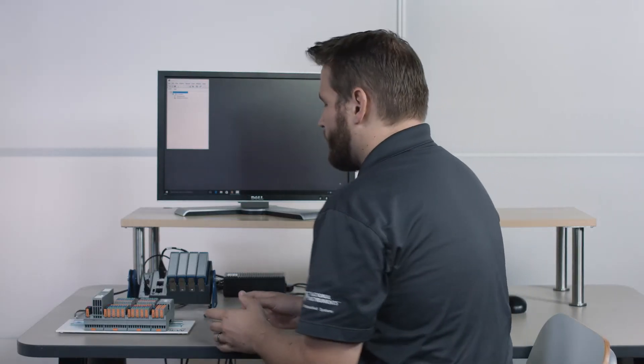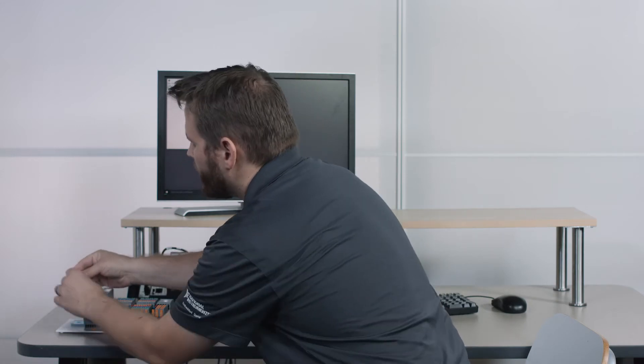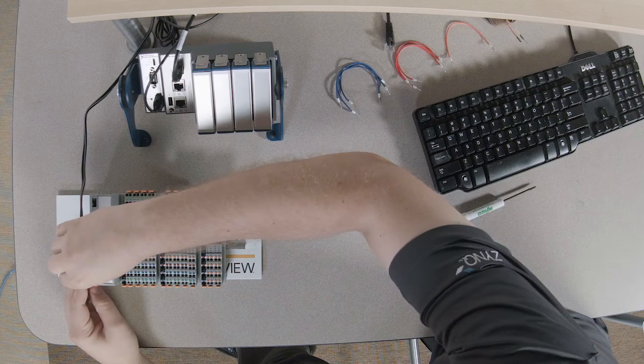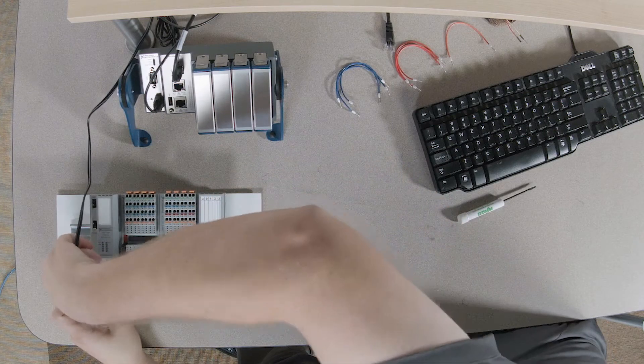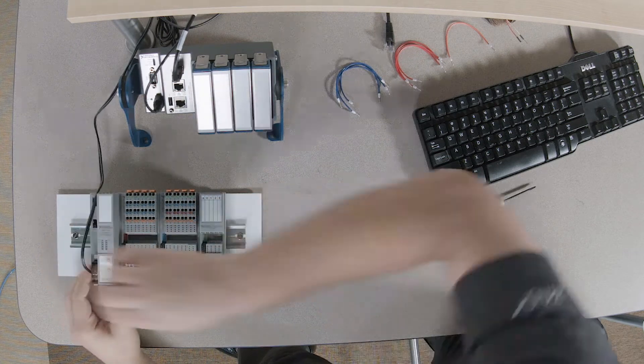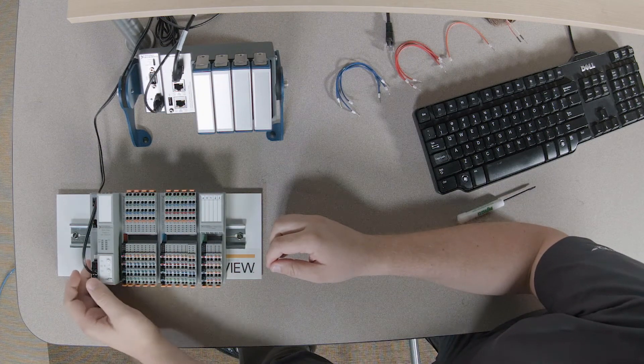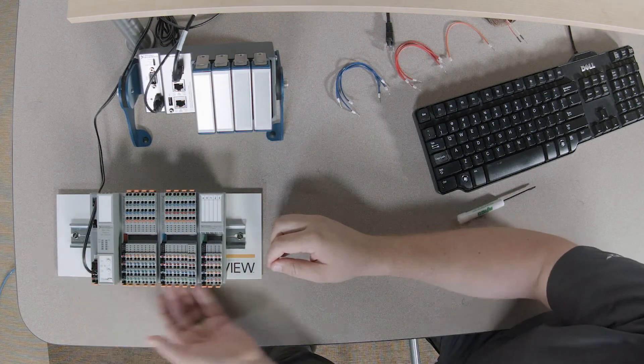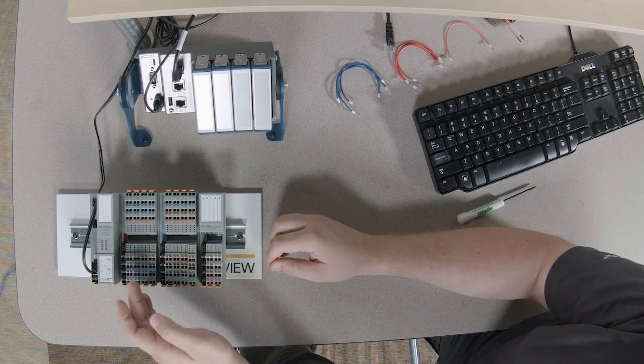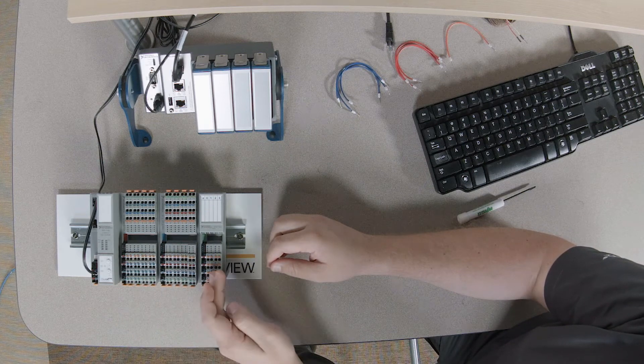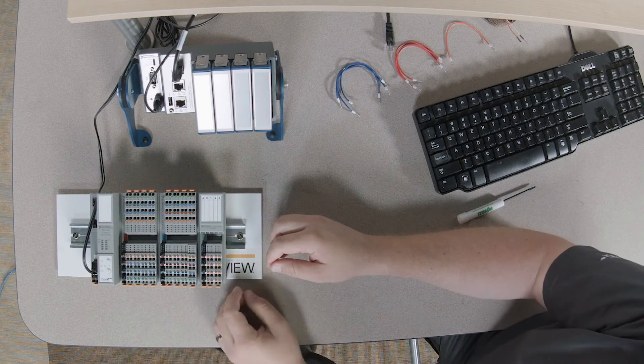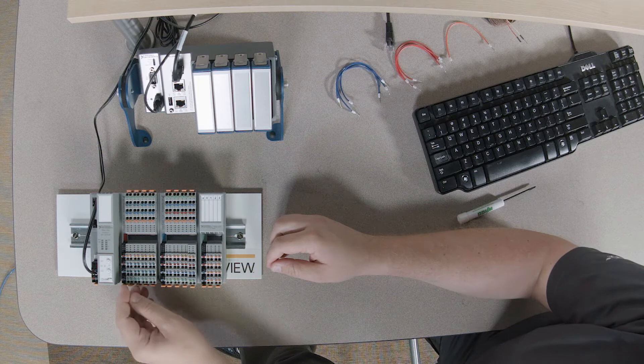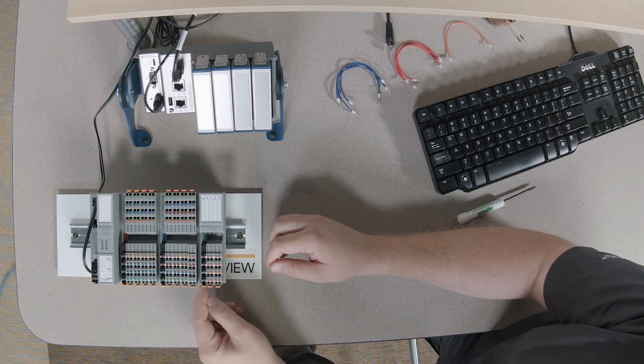So, first thing we want to do to wire is take a power supply and wire it into the bus coupler. So, we'll do that here, and once we've powered the bus coupler, that actually powers that digital backplane as well, but it doesn't power the modules. Each of the modules need their own power. And the power comes in through these little black connectors on the side.